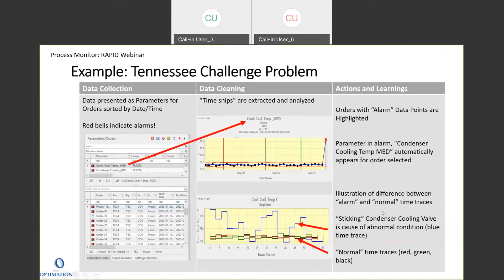You can see how the workflow operates here. It's a quick way — you know there's an alarm, you look at the parameters that are in alarm, look at the control chart, and look at other batches, and you can see what was abnormal. It's a problem that, if you're just looking at time traces for a bunch of parameters, is very difficult to diagnose, but here it's quite simple to find out what was happening.